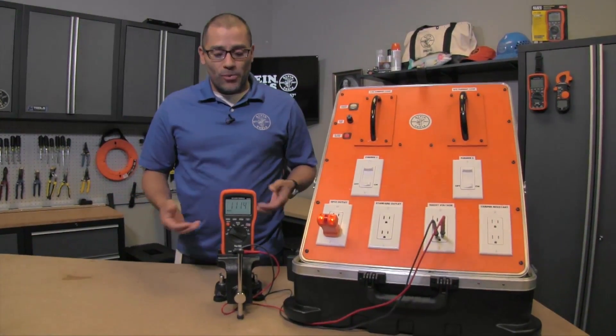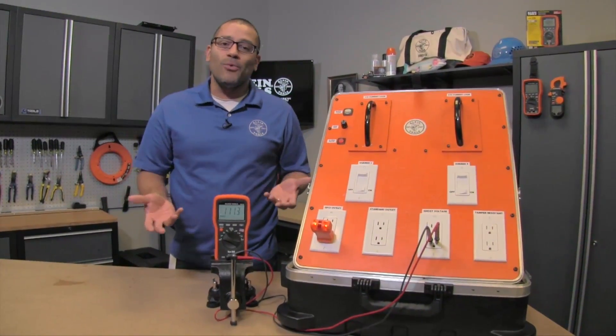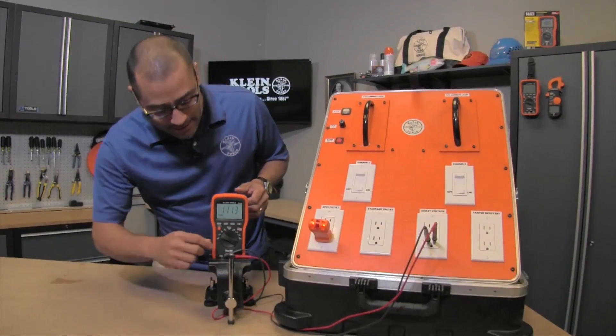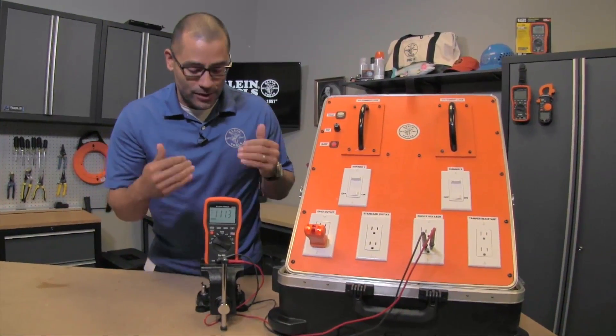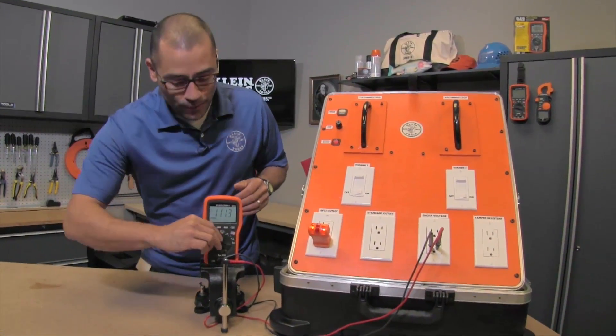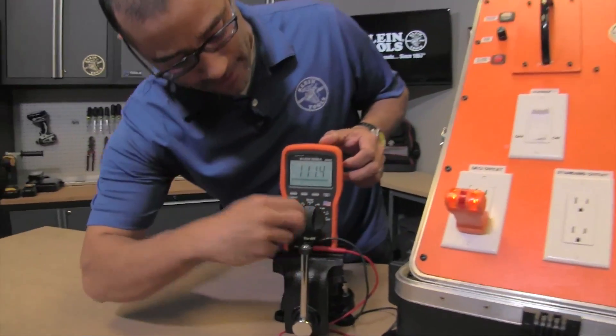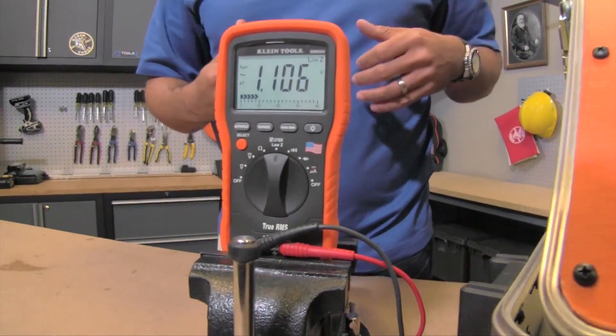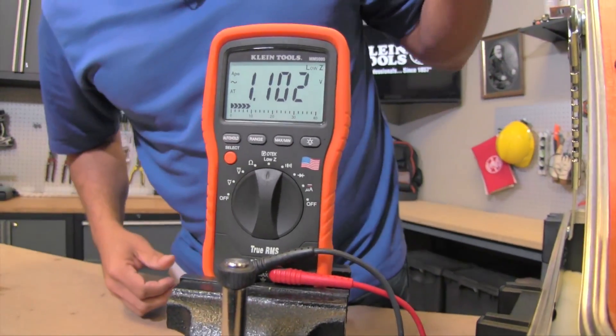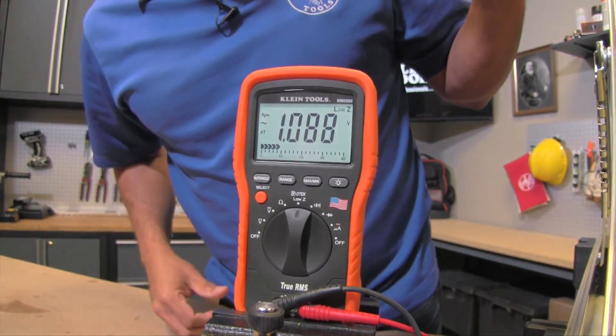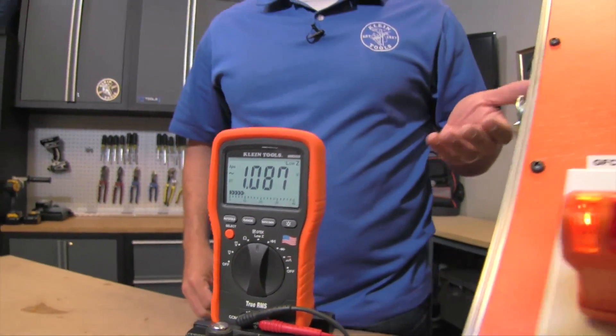So how would you troubleshoot that? Well, low impedance is kind of your way to do that. What it does is it actually simulates a load. There's a thermistor inside the meter, and when you flip to this feature you are actually drawing power now. What you'll notice is out of that same outlet that was reading 109 volts, you'll realize now it's down to about a volt.